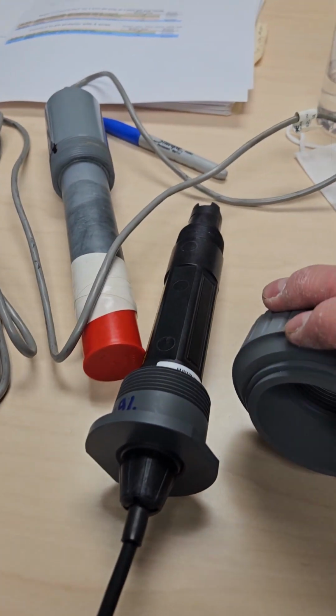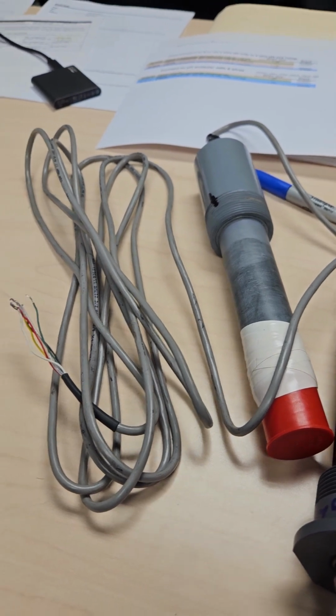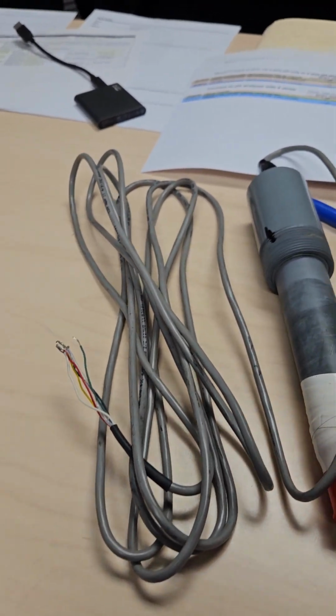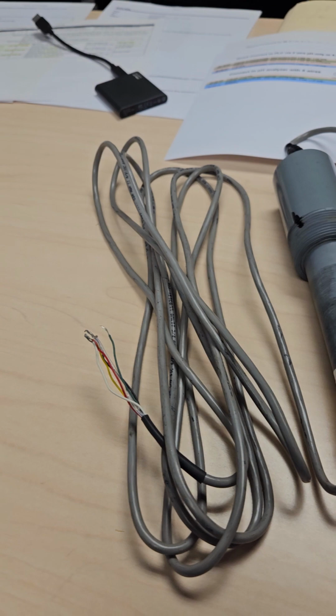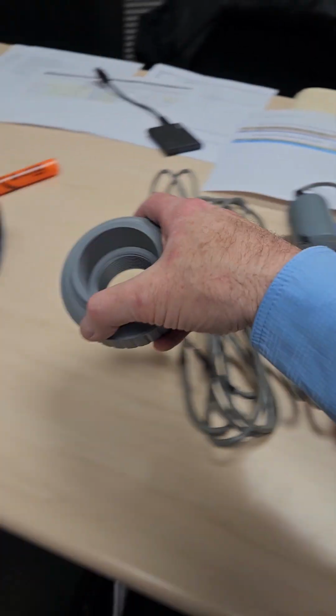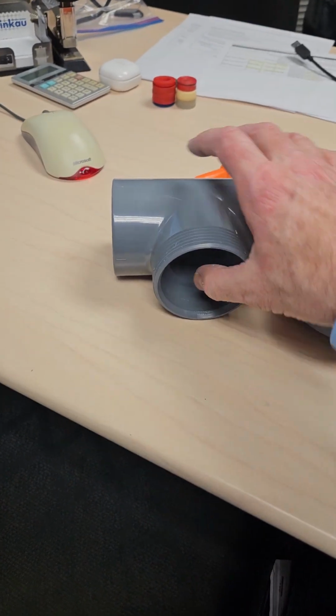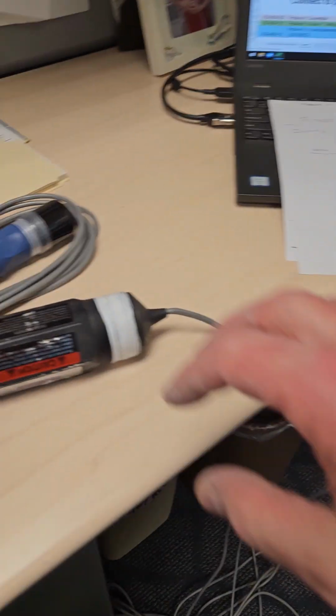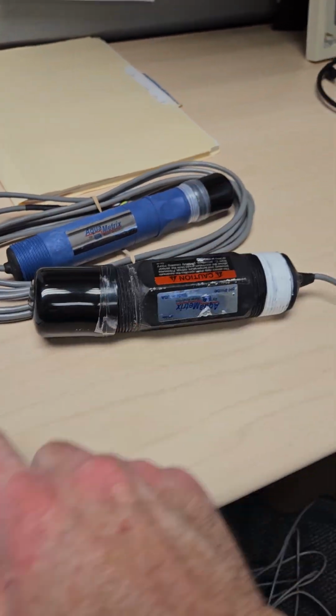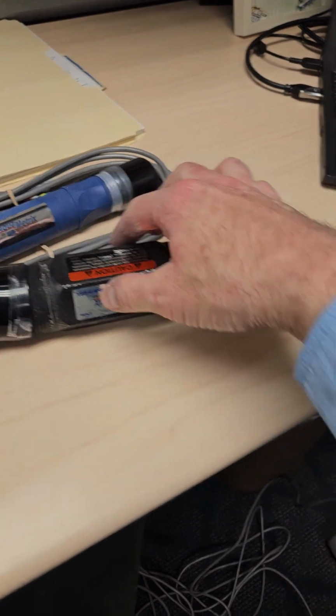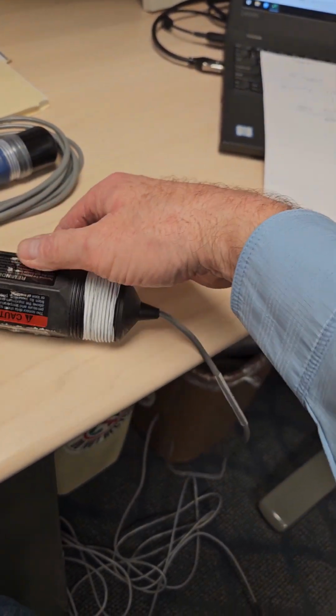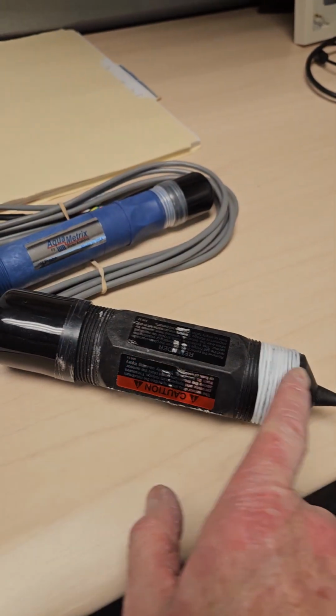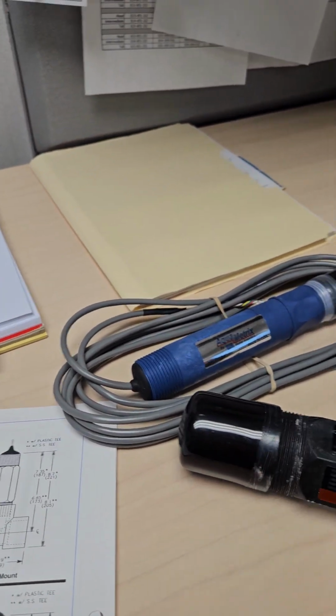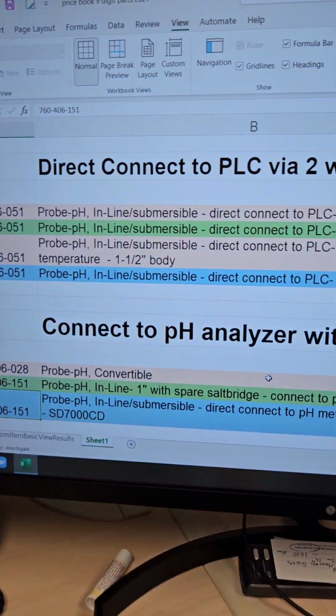Now the new traps are not going to fit in here. This trap threaded in here. These 1 inch probes are too long. No matter what you seem to want to do, even if you put this down at the end, you probably are going to be too far out. So the Union trap is made for either Aquametrics or Sensorex probes that have this crayon-shaped or octagon-shaped body and threading on both sides, but we're threading it on the end. So we have different type probes.